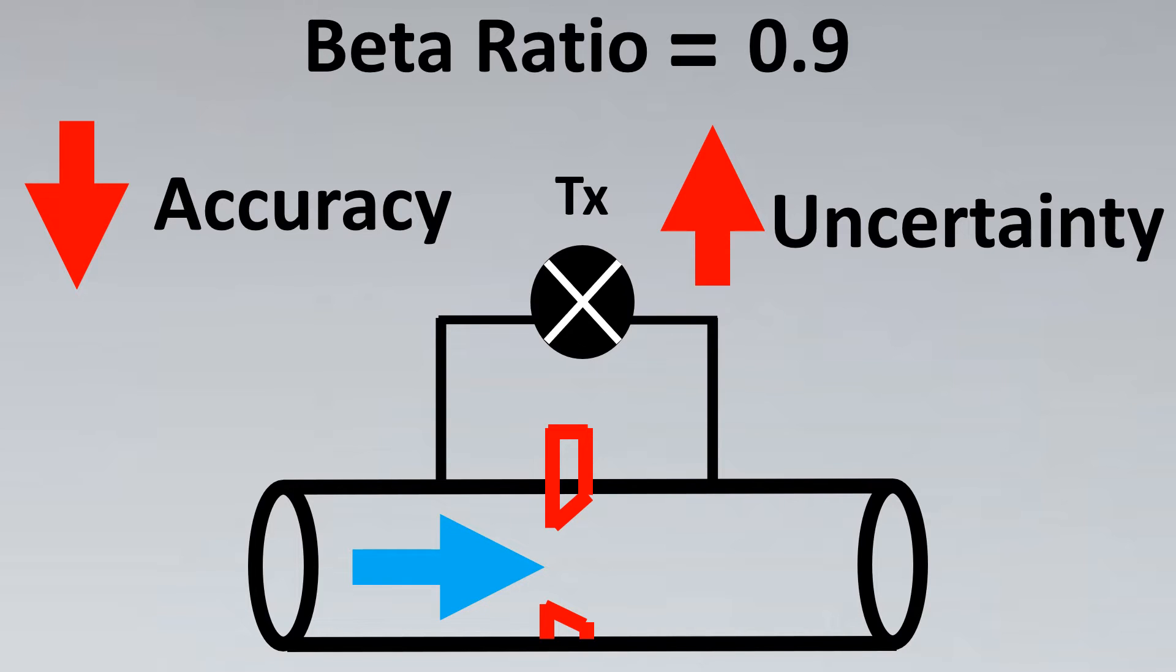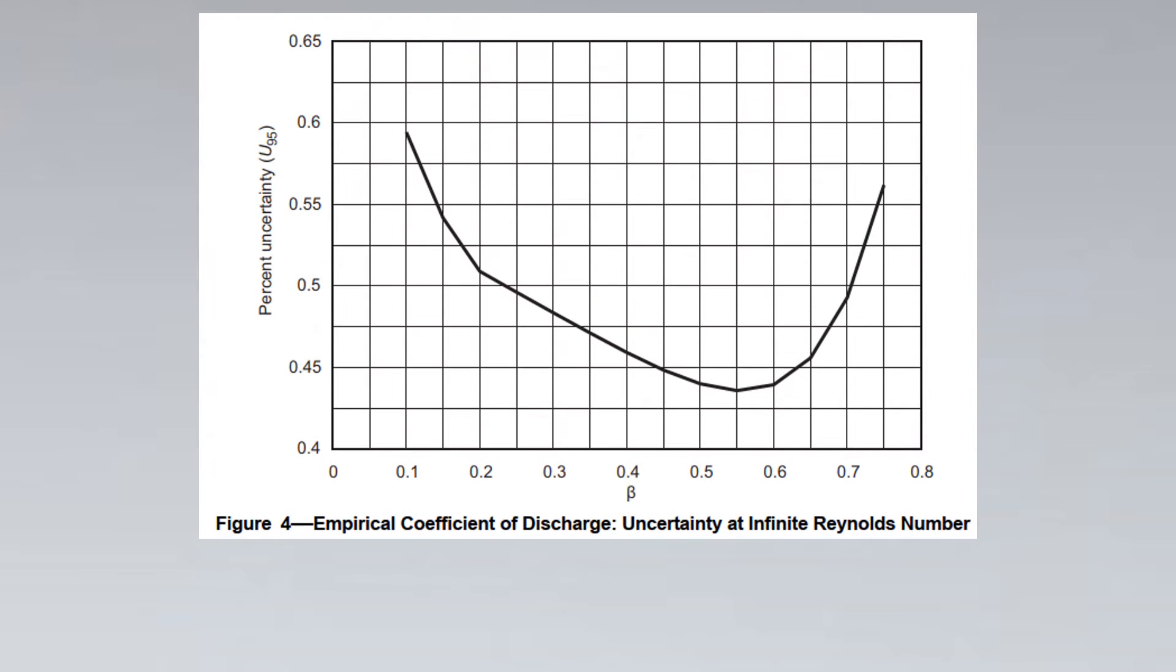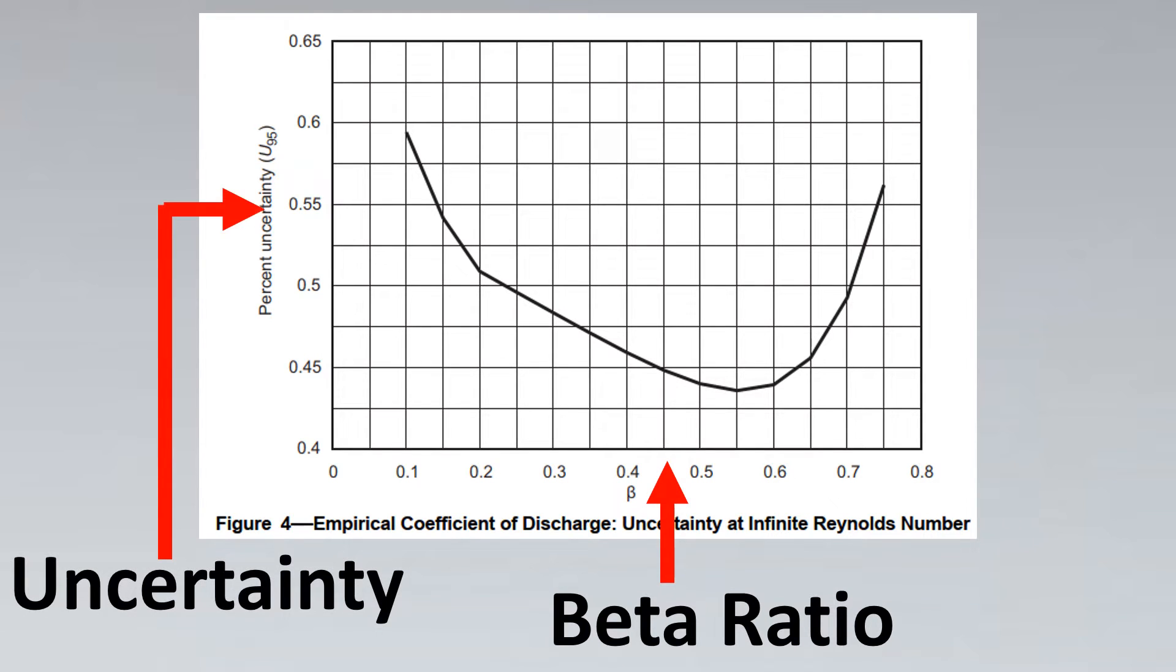This is an amazing concept explained by API standard. API MPMS is one of the most important standards when it comes to orifice. It has the concepts explained in a very simple fashion. Now let's look at a graph which is given by the standard. So here the x-axis has beta ratio and the y-axis has uncertainty. Here we'll see that our range is between 0.3 to 0.6. So this is our range, and if you notice, for this range the uncertainty coefficient is very low. So for this range you see it is the least in the graph.